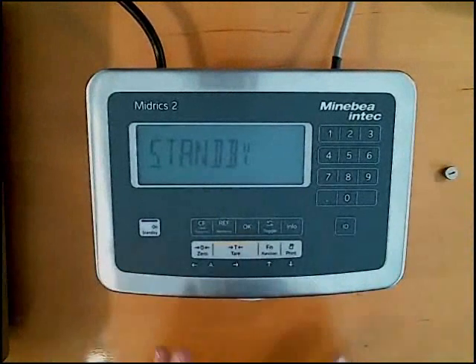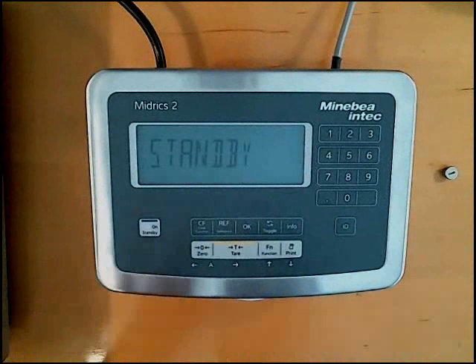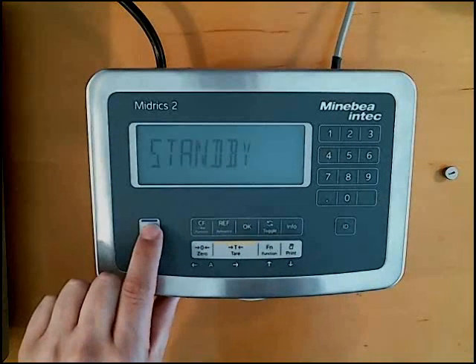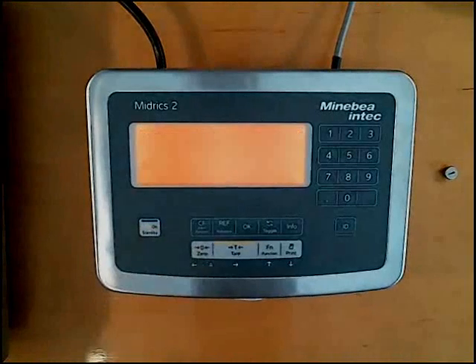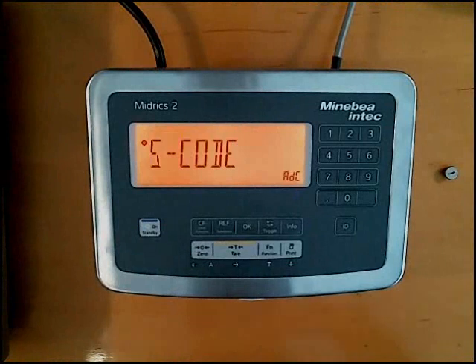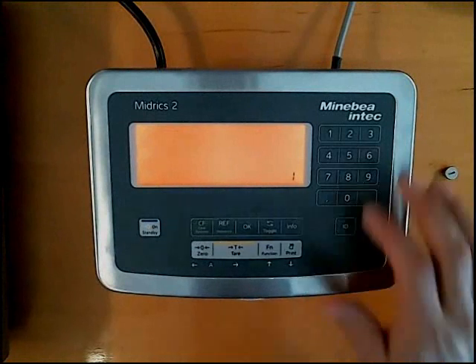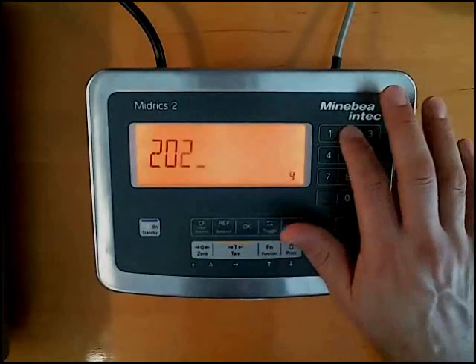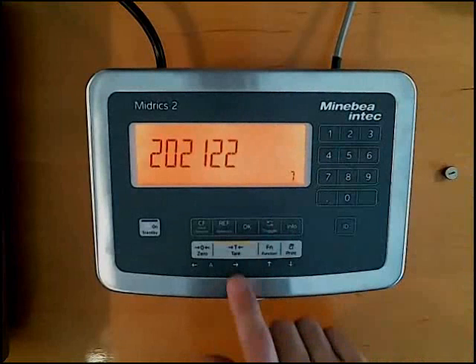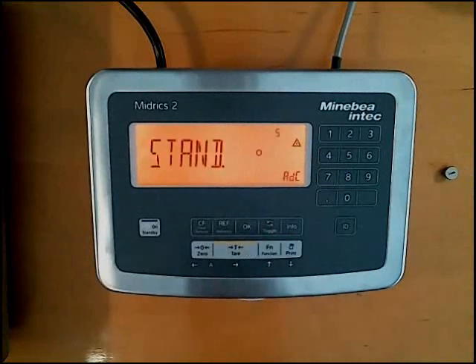Once you ensure that the switch is in the right position, all you have to do is start with the unit off, turn it on, and press and release the 0 key during the segment check. At this point, you'll see ADC con and S code flash for a second, and then you'll be right here on this screen where there's a flashing cursor. At this point, you'll type in the service password, which is 202122. So go ahead and use the numeric keypad, and then press the tare key. Think of the tare key as enter.